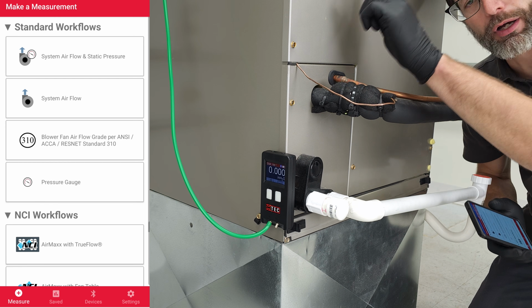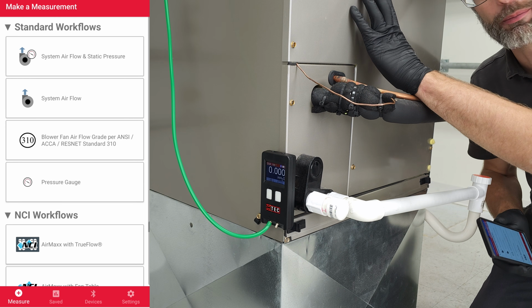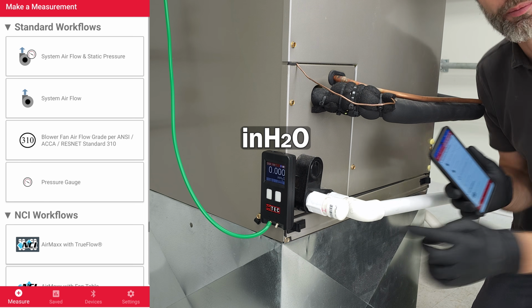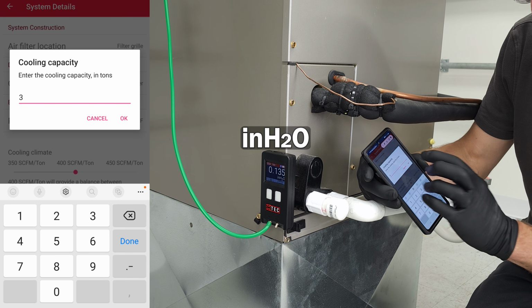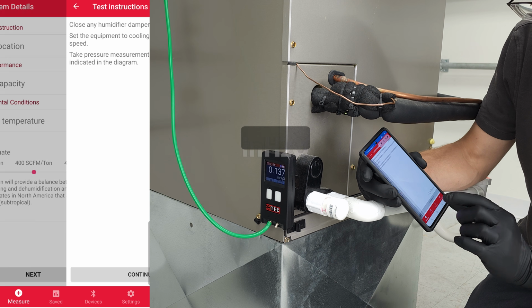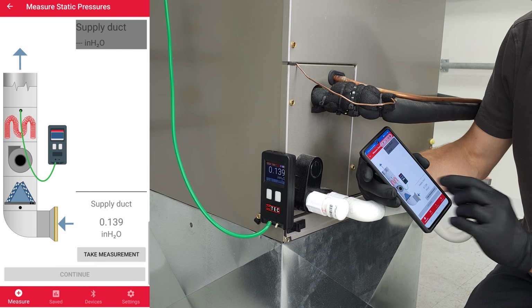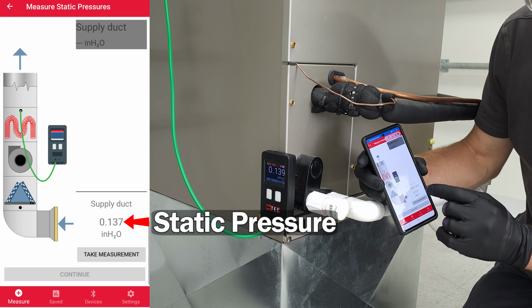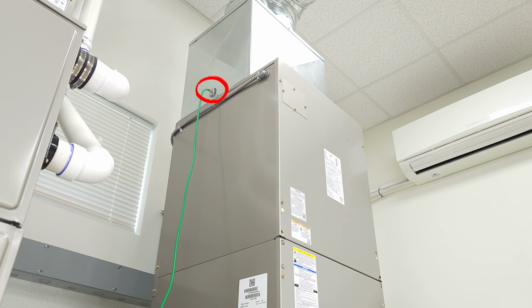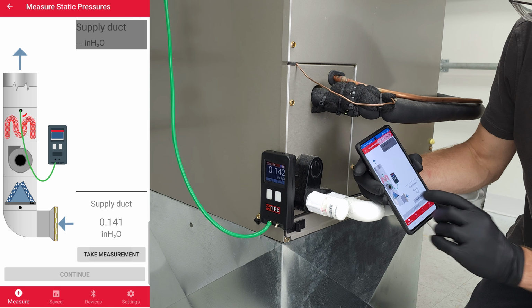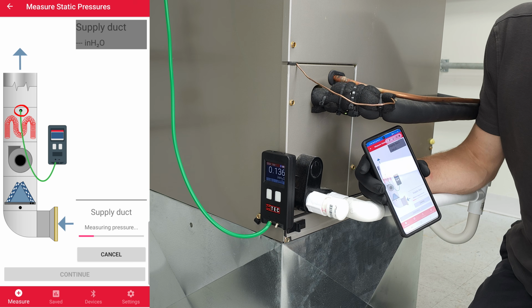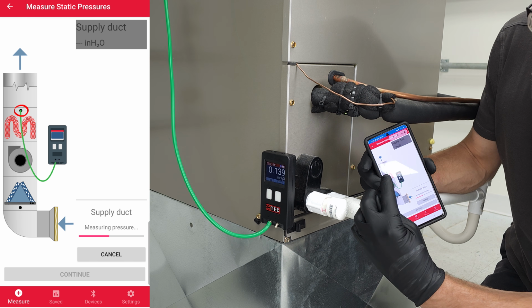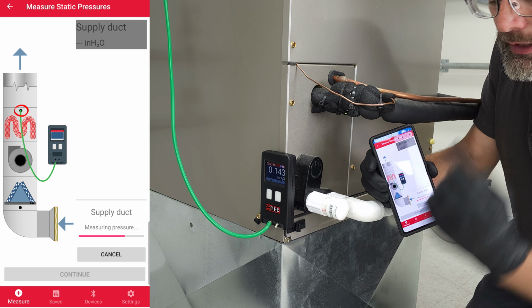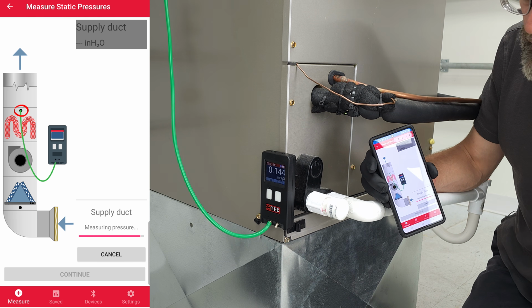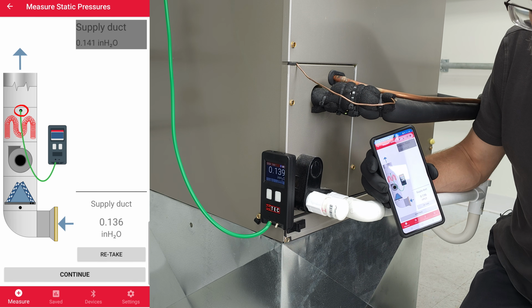So now we put the top cover plate back on the unit, and we're going to turn the power back on, and we're going to measure our inches of water column in the supply with our app. So we're just filling out this information again. And you can see our static pressure is 0.13 with our static pressure tip. That's inserted right in the supply plenum. And so we're going to take our measurement. And so this is showing in the air handler right above the electric strip heating. This one doesn't have any electric strip heating in it. And we put our hole right in the plenum, which you can always put a cap in there, a duct plug, after you're done. Okay, so continue.